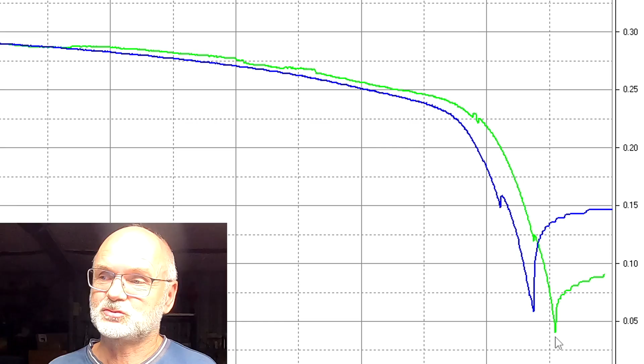But guys, I must say these curves look almost identical to me. There's not much difference, not much gain from certified cells. Even at 200 amps it doesn't make a big difference, we're not seeing a big voltage sag anywhere. 200 amps, 1 hour 10 minutes of full power discharging, heating the batteries up to almost 45 degrees, and there's no difference.